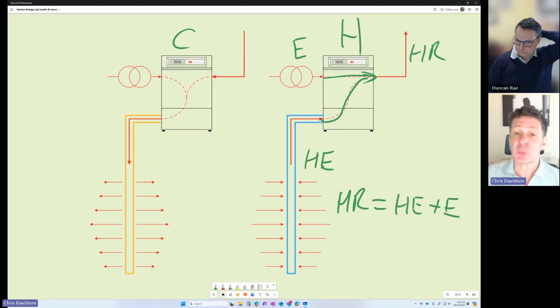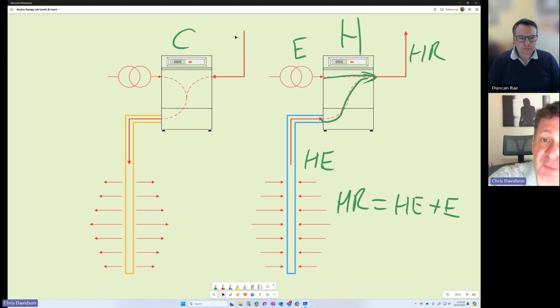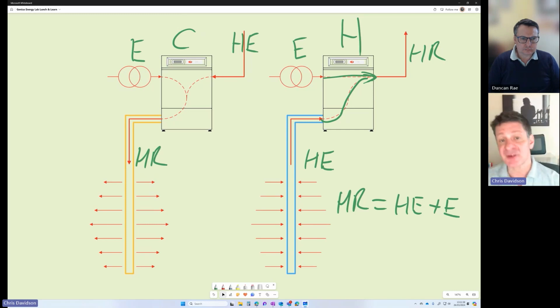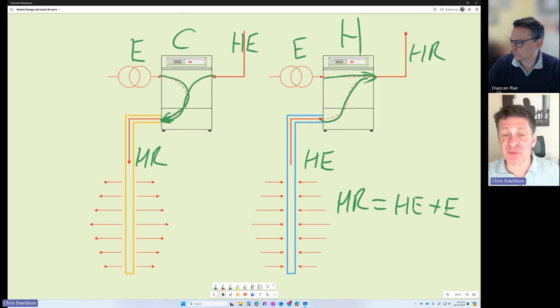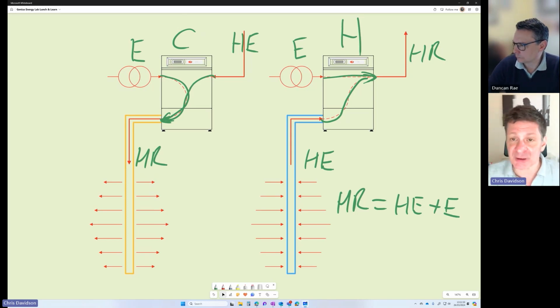In cooling mode, we're extracting heat, but this time from the building, so our heat of extraction is in the building and our heat of rejection is into the ground. Again we've got that electrical consumption, and again through friction that ends up as heat going into the ground this time, added to the heat taken from the building. So in a very real way, the electrical energy consumed by the heat pump contributes to heating the building and actually hinders the cooling of the building.